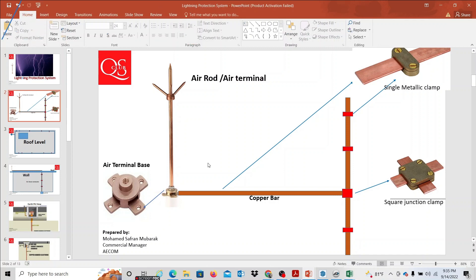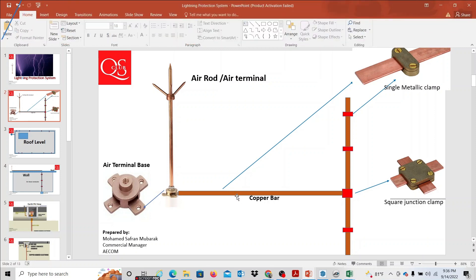This is a technical point: if you have no base, a question will arise about where the rod base is. The air terminal and air rod base are both required. The copper bar dimension is 25 mm by 3 mm — 25 mm is the width and 3 mm is the thickness. The copper bar components include T-junction and cross junction.